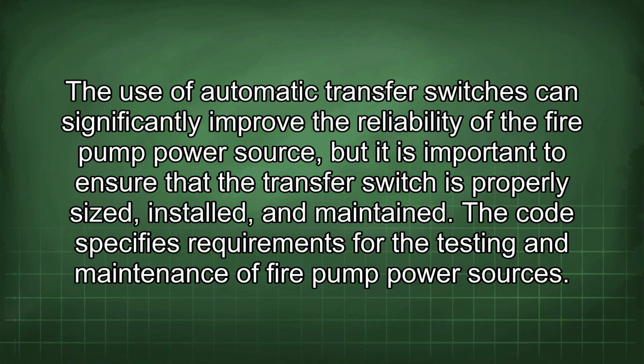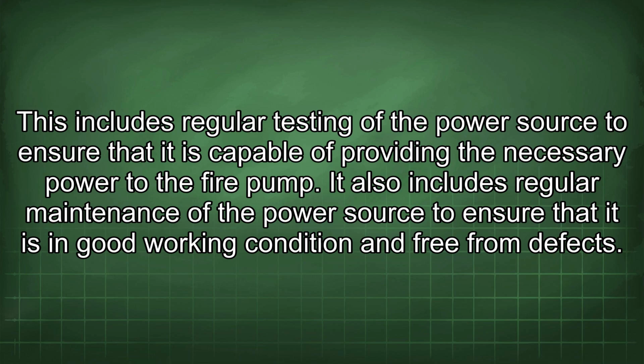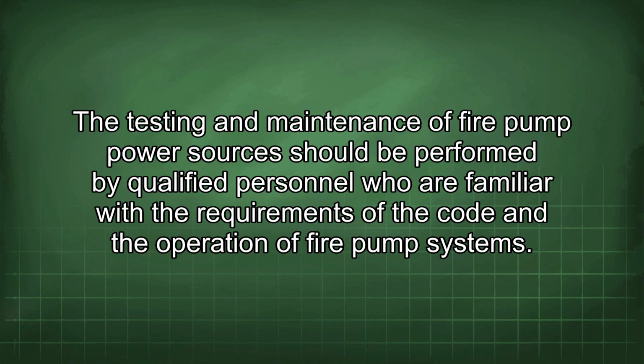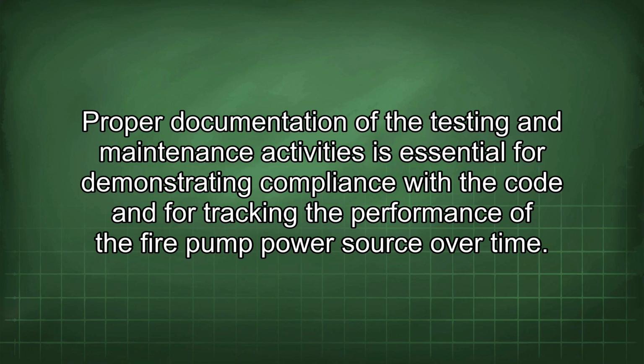The code specifies requirements for the testing and maintenance of fire pump power sources. This includes regular testing of the power source to ensure that it is capable of providing the necessary power to the fire pump. It also includes regular maintenance of the power source to ensure that it is in good working condition and free from defects. The testing and maintenance of fire pump power sources should be performed by qualified personnel who are familiar with the requirements of the code and the operation of fire pump systems. Proper documentation of the testing and maintenance activities is essential for demonstrating compliance with the code and for tracking the performance of the fire pump power source over time.